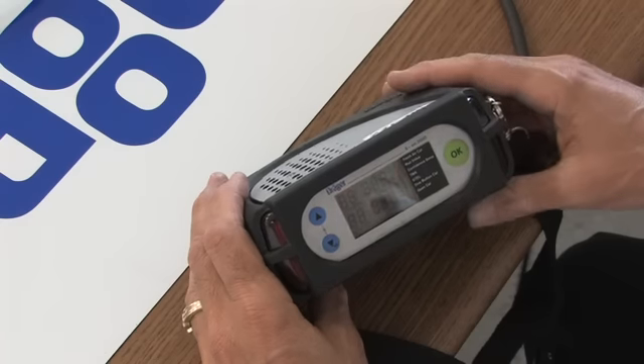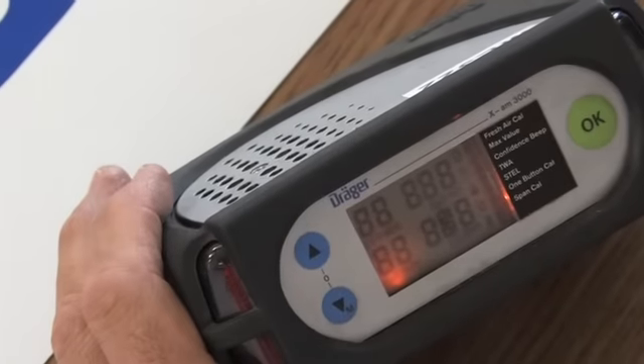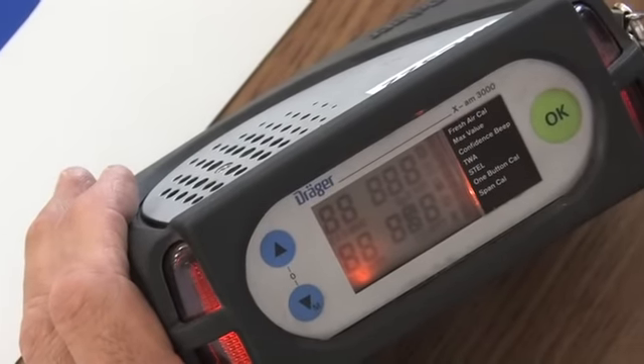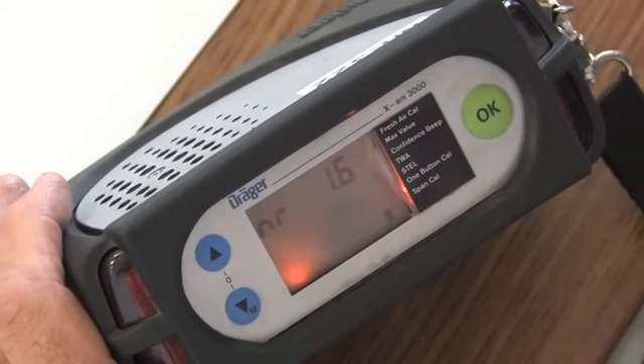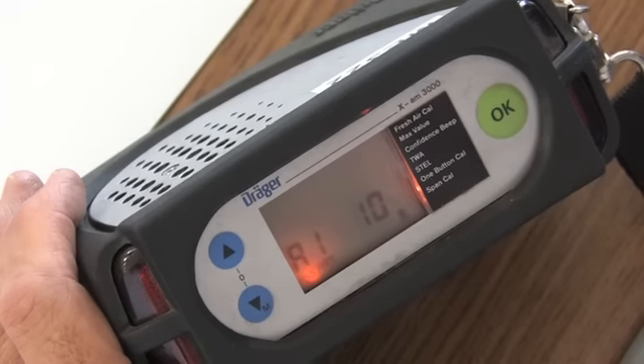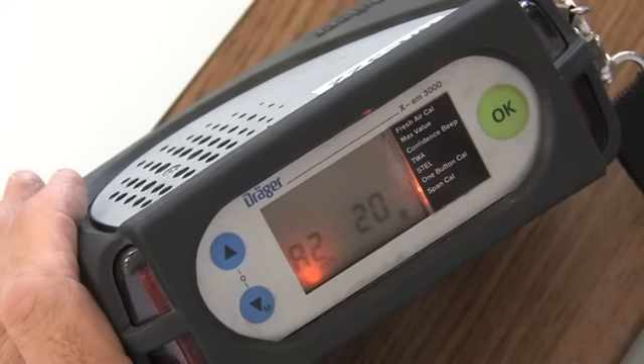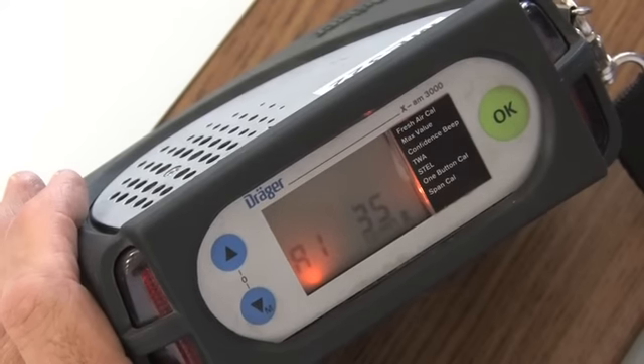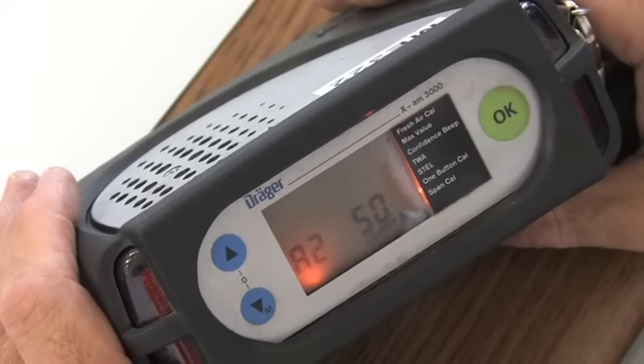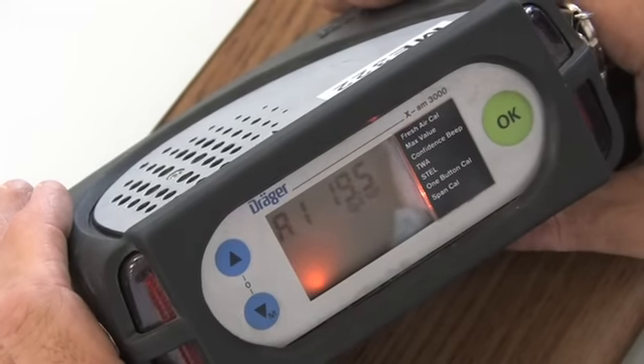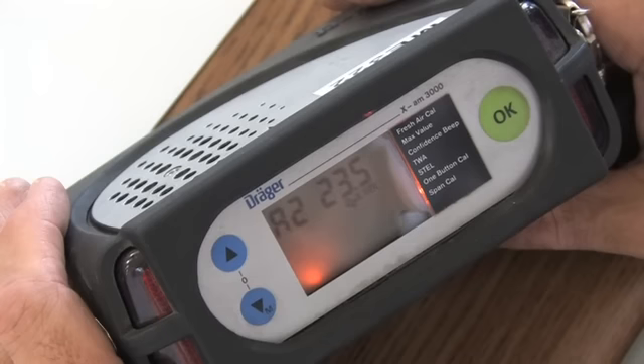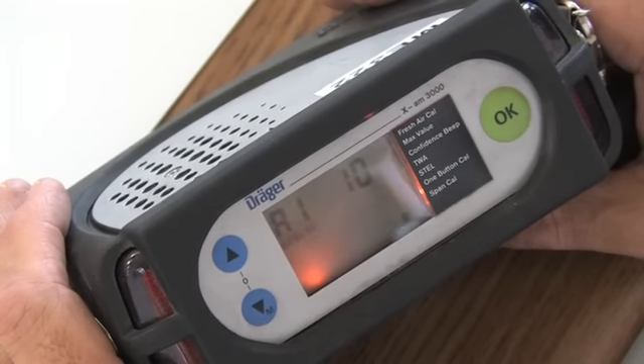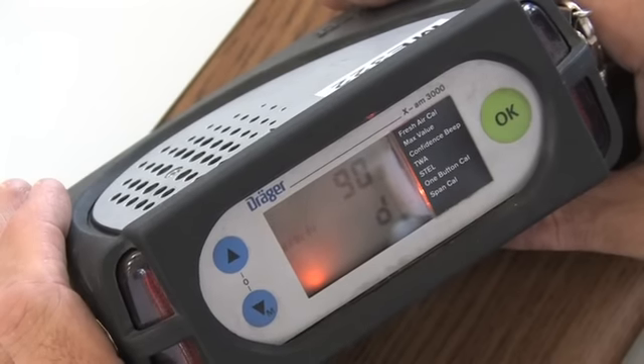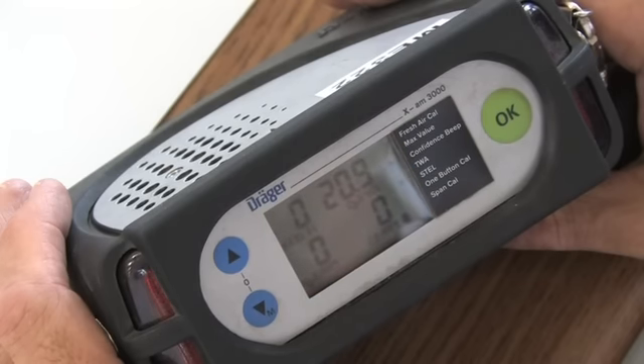Starts up. Notice the battery on startup was full. That's the way you check the battery on this instrument, if you want to check it before it turns on, is while you're pushing the OK button and it's going 3, 2, 1, you see that the battery was full. You can let go of the on button and it won't start up. So that's how you check the battery if you're only interested in checking the battery. Then it goes through its warm-up and it tells you where all the A1 alarms are and where all the A2 alarms are. A1 is your first threshold, A2 is your second threshold, and latching alarm. And this says I have 90 days before calibration is due. And then it gives me the gases.